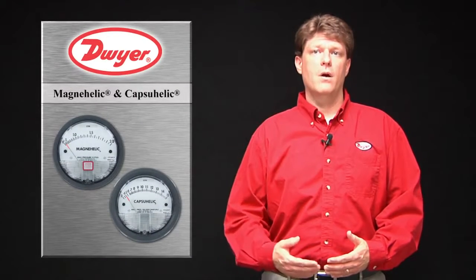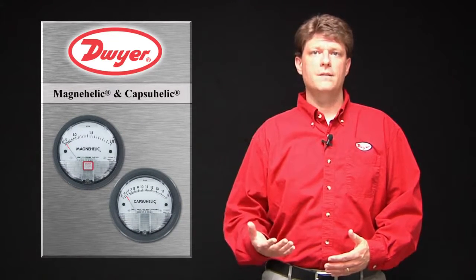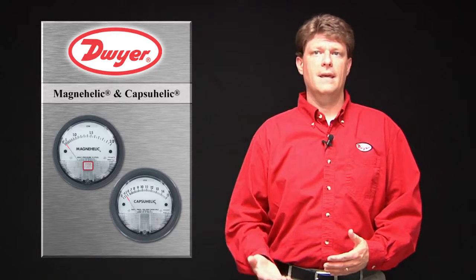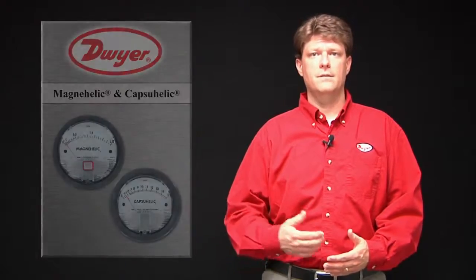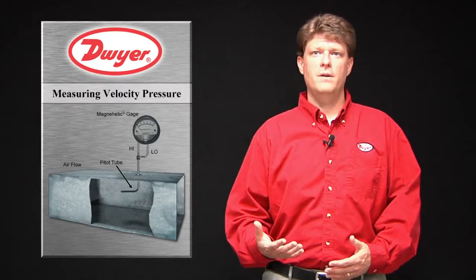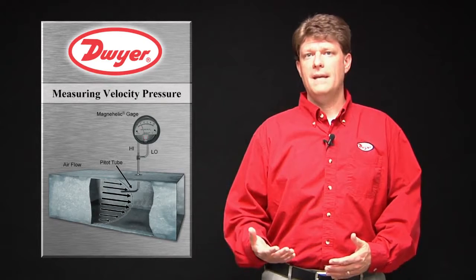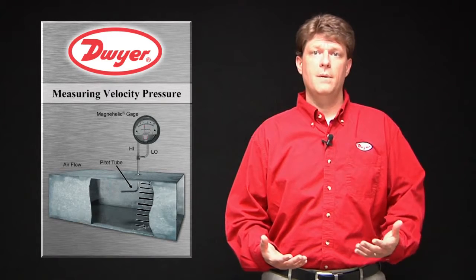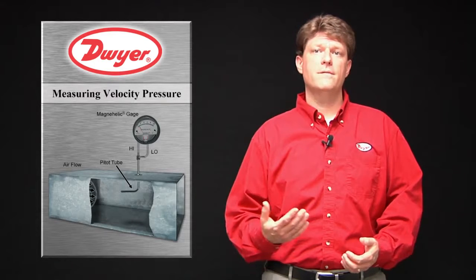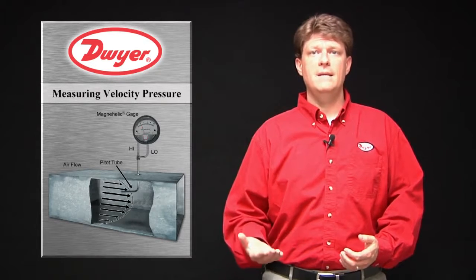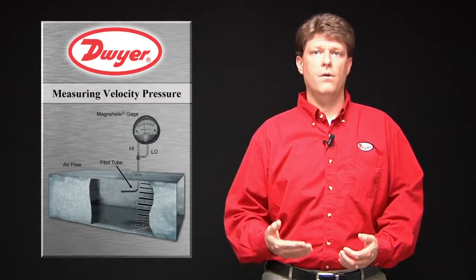In this video I will cover direct reading scales for velocity or flow rate on the Magnehelic and Capsuhelic differential pressure gauges. A common flow measuring application is using a Magnehelic gauge with a pitot tube to measure velocity pressure. This velocity pressure can then be easily converted into velocity or flow rate.